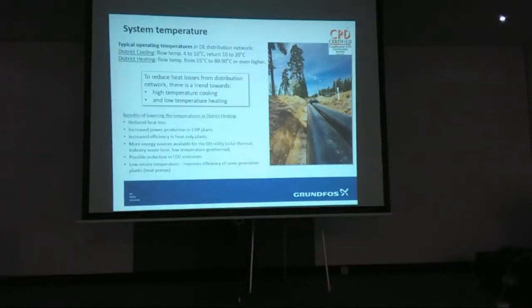So what benefits have we got by lowering the temperatures? Reduced heat loss. So if you've got a 10% loss over 5 or 6 miles, you've only got 10% of a small value, I suppose. You can get more out of the CHP and serve more people, because you've got higher values here you can put into a district, into a thermal store, and then more people can have access to lower temperatures.